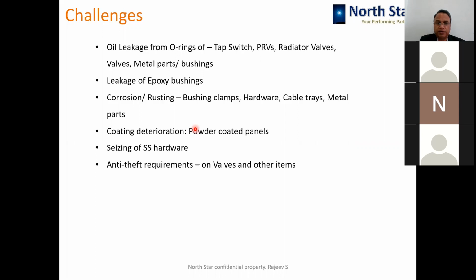The anti-theft requirements on valves and other items which customer wants sometimes, and providing those can be a challenge. The sharp edges on punched washers is a very small issue, but can create damage to the paint, and from there rusting can start. A 50 paisa washer can damage your transformer cover or tank body severely, and the rusting can spread throughout, and the damage can be very severe.